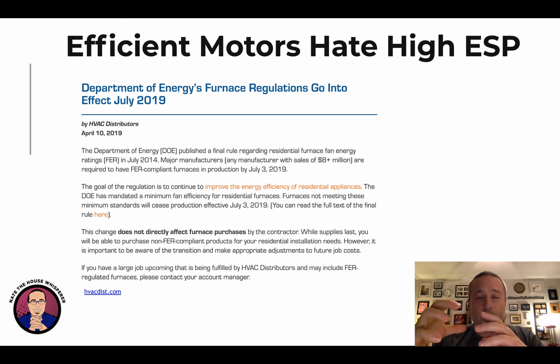What needs to happen, and what has happened, is in July 2019 every furnace was required to have an ECM motor put into it. So any high volume furnace—basically anything a normal consumer is going to buy—has an ECM motor now. We're hearing of a number of failures already. This only happened about 1.5 years ago as I'm recording this, and we're already getting failures after 1 or maybe 2 heating seasons, because we're putting ECMs into situations where they are not happy. This is a real problem.